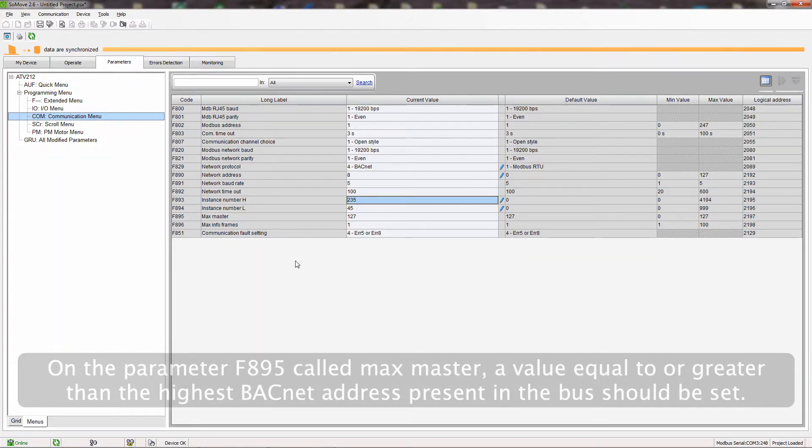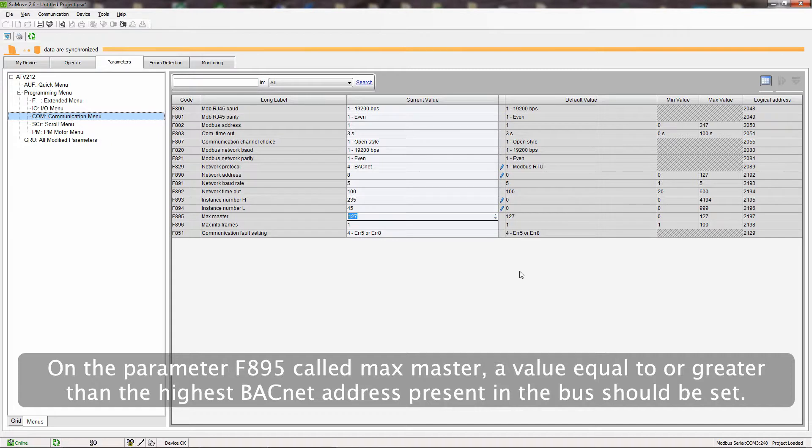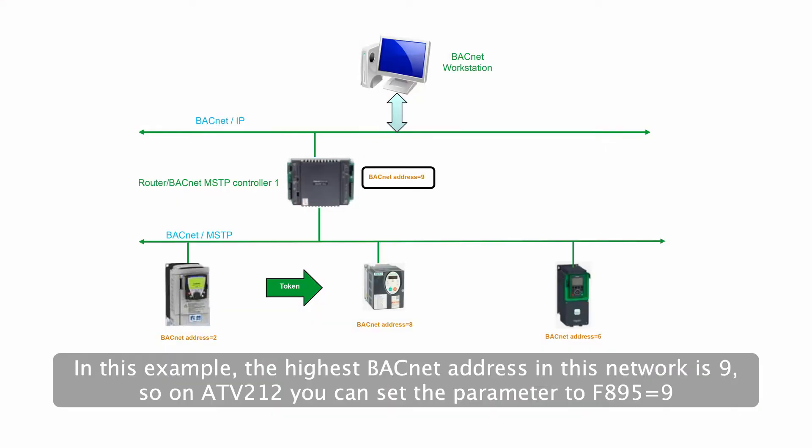On the parameter F895 called MaxMaster, a value equal to or greater than the highest BACnet address present in the bus should be set. In this example, the highest BACnet address in this network is 9, so on ATV212 you can set the parameter to F895 equals 9.